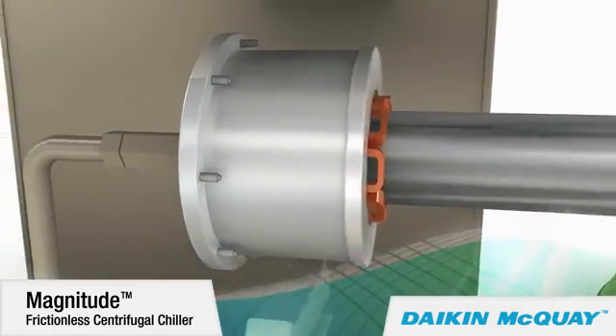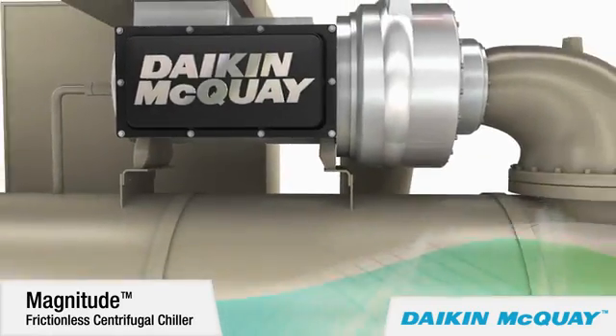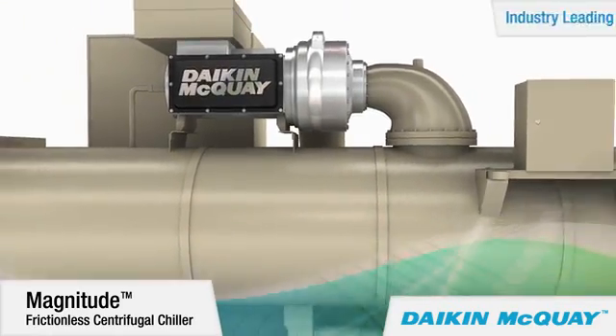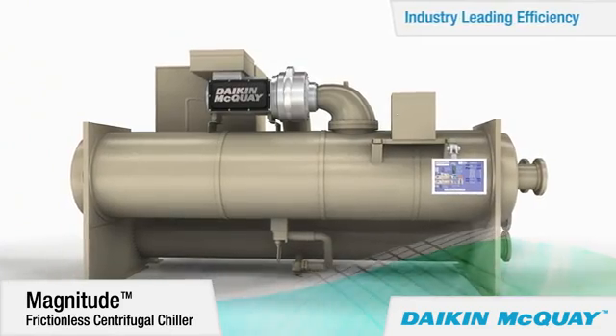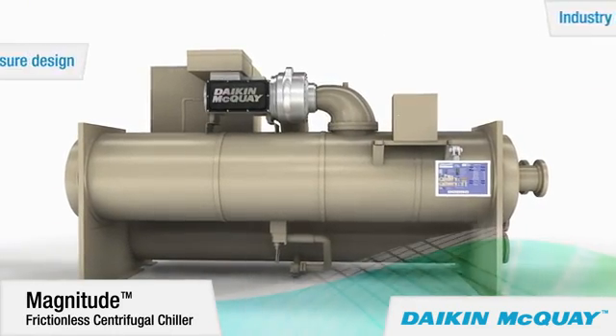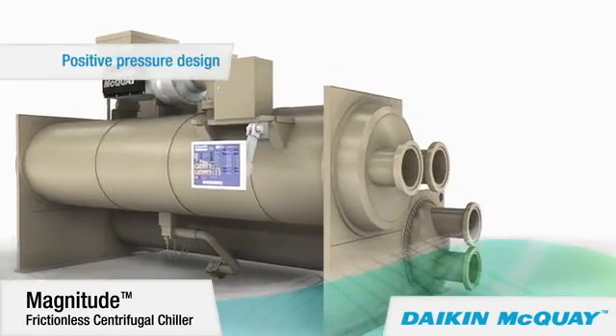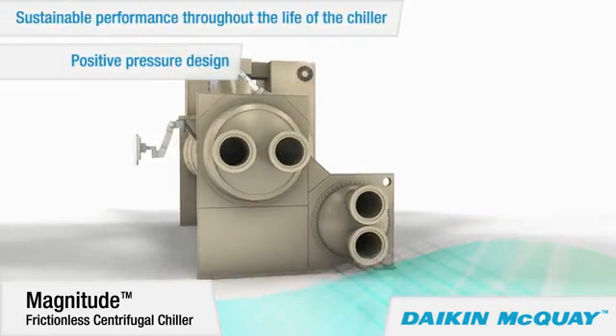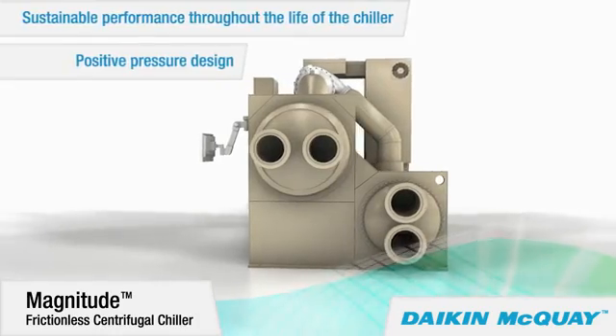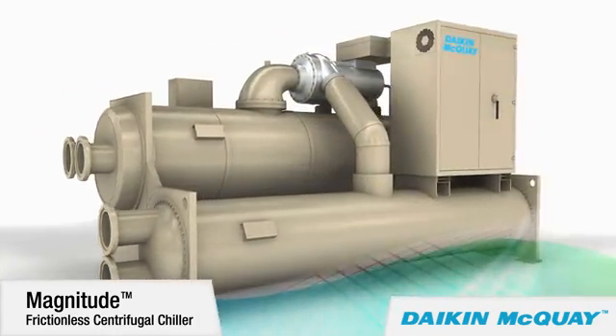As a result of its advanced compressor with an integrated variable frequency drive, the magnitude chiller delivers industry-leading efficiency. With its positive pressure oil-free design, that industry-leading efficiency can be sustained throughout the life of the magnitude chiller because there's no oil to contaminate the chiller refrigerant. Eliminating the oil management system also reduces the associated maintenance cost.